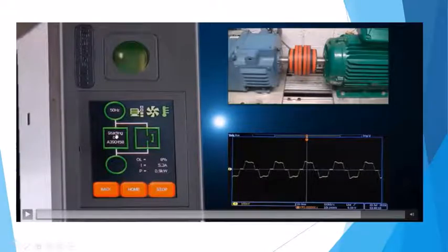This is still in the mode of the thyristor. So this is actually compensating the current to the motor. You can leave it in this state, in automatic compensation, and look at the total power that it's drawing. And then when it kicks over, it'll actually give you the full sine wave back. But the benefit of this is it does give you added savings. And that's what Nolan was originally pushing, is the savings.